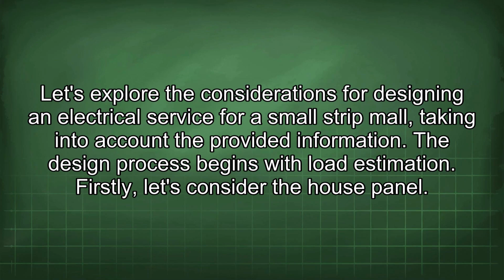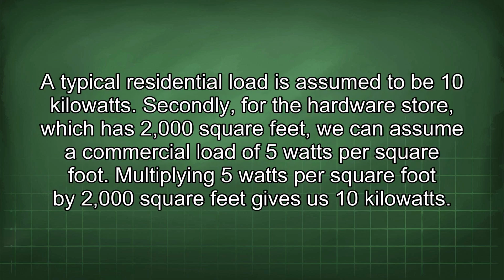Let's explore the considerations for designing an electrical service for a small strip mall, taking into account the provided information. The design process begins with load estimation. Firstly, let's consider the house panel. A typical residential load is assumed to be 10 kilowatts. Secondly, for the hardware store, which has 2,000 square feet, we can assume a commercial load of 5 watts per square foot. Multiplying 5 watts per square foot by 2,000 square feet gives us 10 kilowatts.